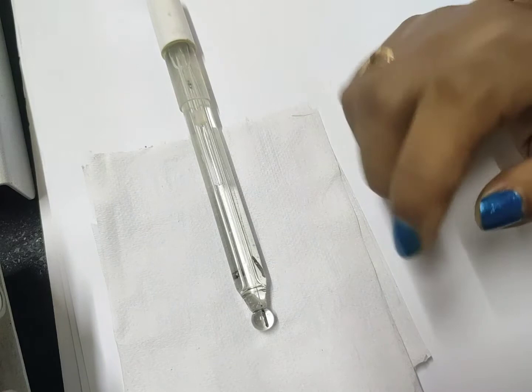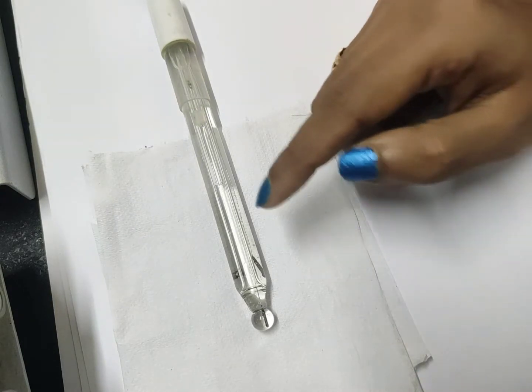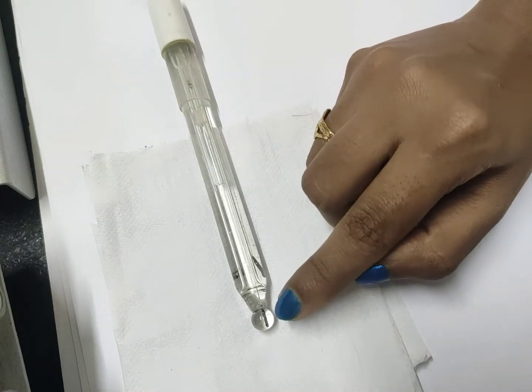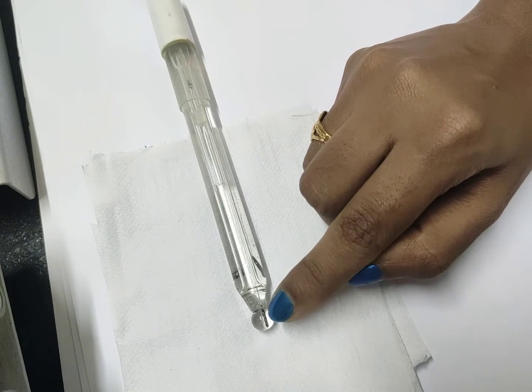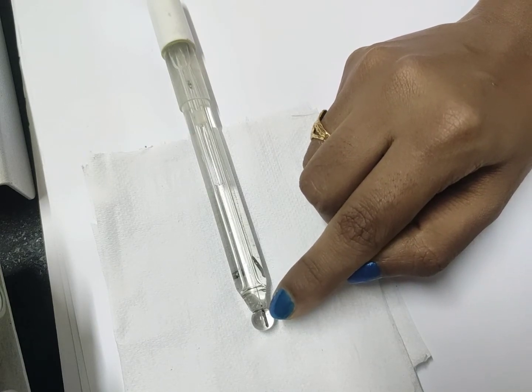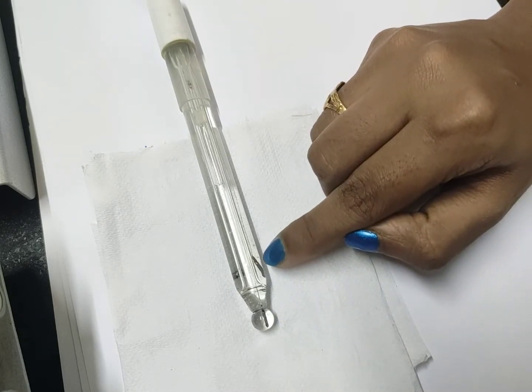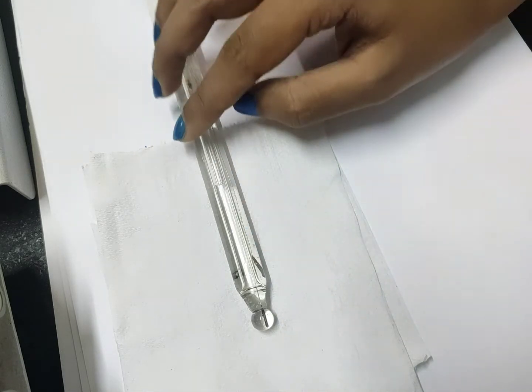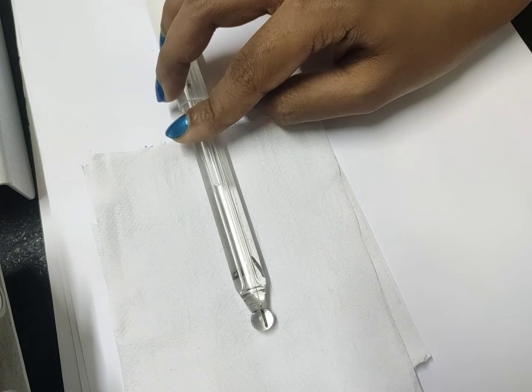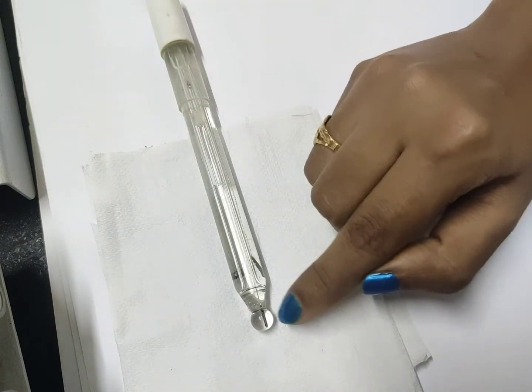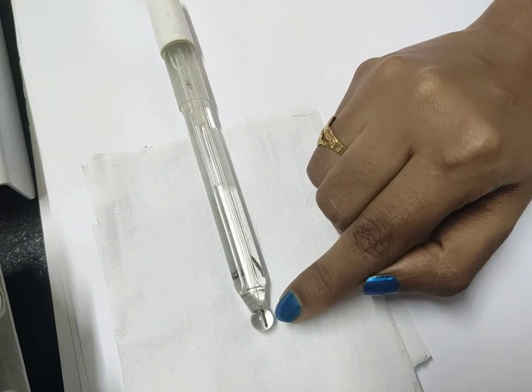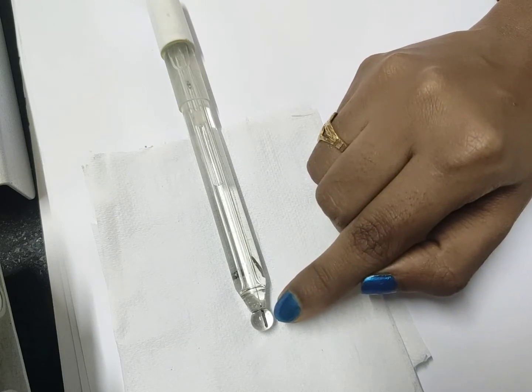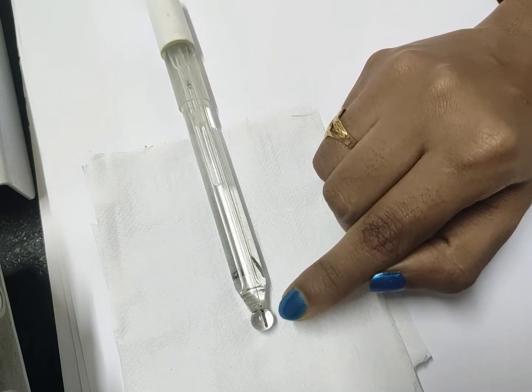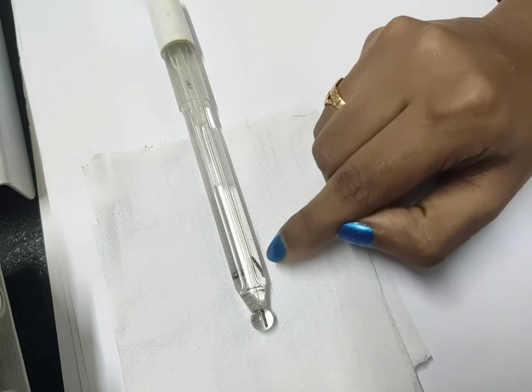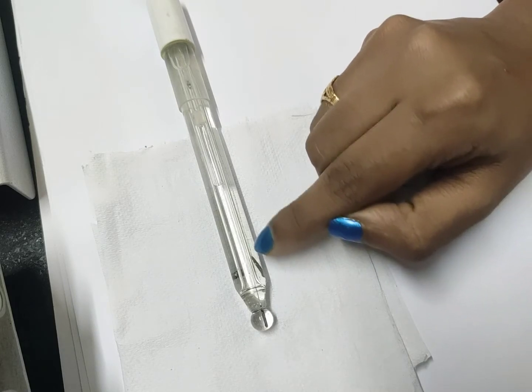First let us see what electrodes are present inside this probe. Here, inside this glass bulb, there is one electrode, which is made up of silver chloride, and similarly one more is present here. So there are two electrodes present inside this pH probe. The electrode that you can see in the glass bulb is called the sensing electrode or indicator electrode, and this one which you can see here is called the reference electrode.